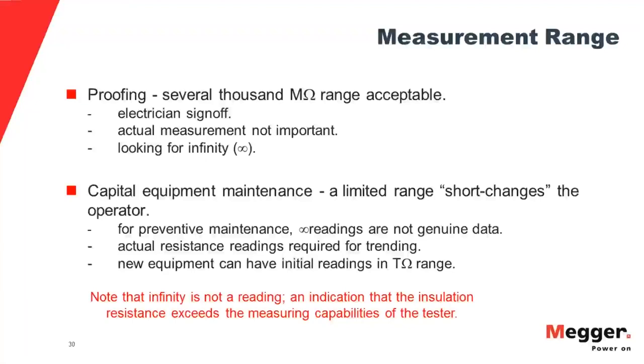There is simple go, no-go testing, where all you need to do is determine whether something is good or bad. This would be like an electrician signing off a job. In those cases, you can buy relatively simple, relatively inexpensive insulation testers that give you enough range. The old, what we call major Meggers, typically went up to about 2 gigohms. Nothing is bad at 2 gigohms.